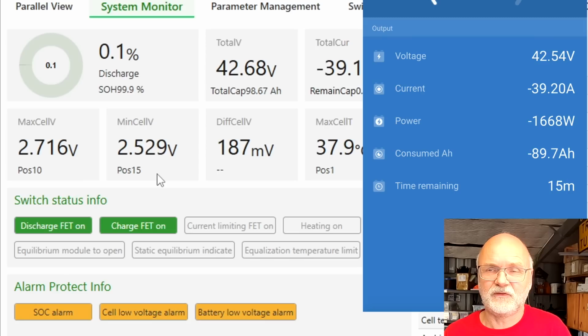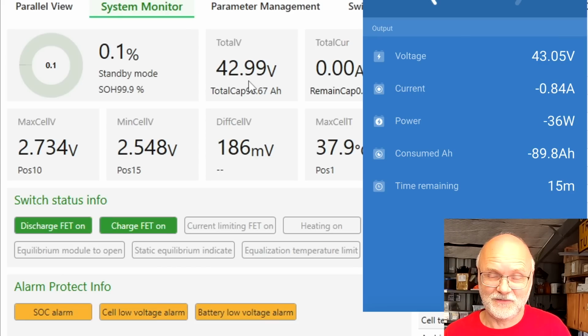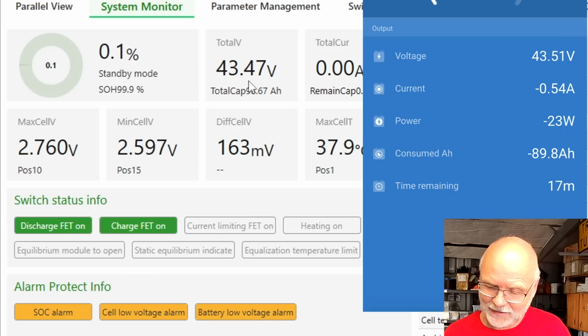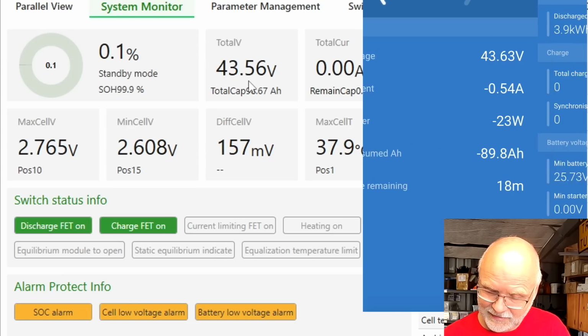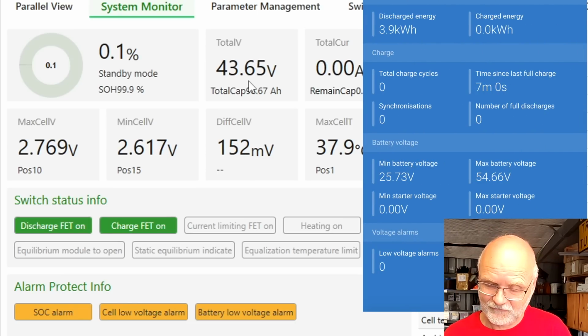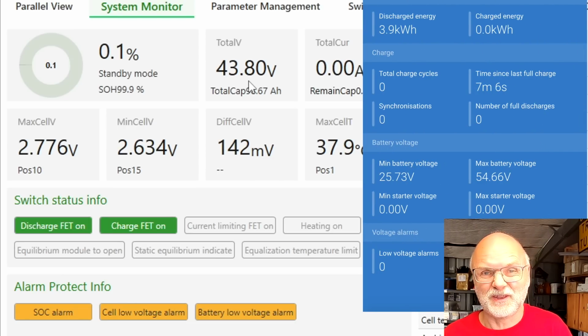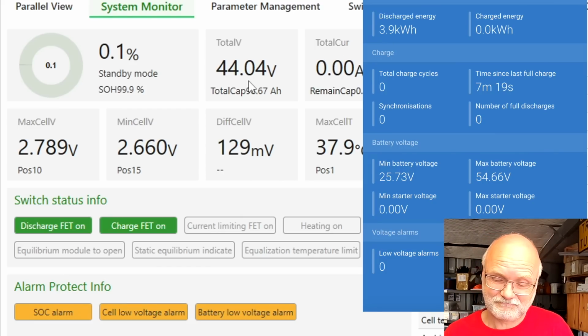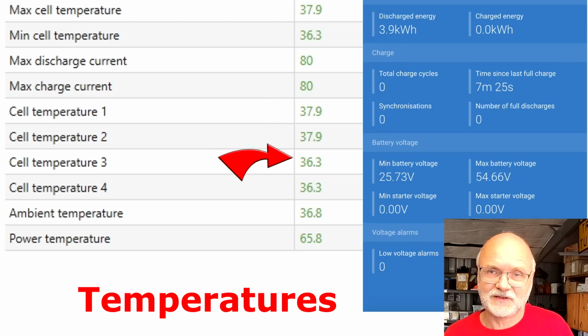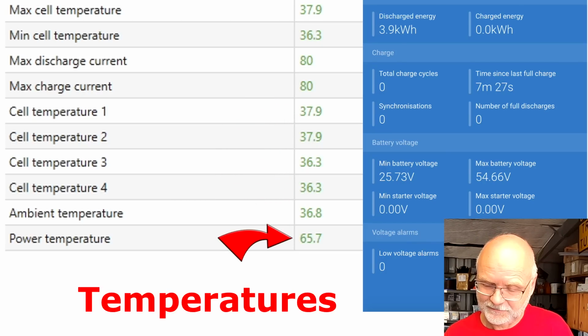2.5. Cell number 15 will be our disconnect. Or the inverter shuts down before that. The inverter has shut down, the Xia inverter has shut down. So all the load is gone. We have pulled almost 90 ampere hours out of the 100 ampere hours and 3.9 kilowatt hours of energy. It is quite a bit short actually to the claimed 5.1 kilowatt hours, but we drove the battery with almost 1C, so it is actually expected that the battery doesn't deliver the full capacity or energy.